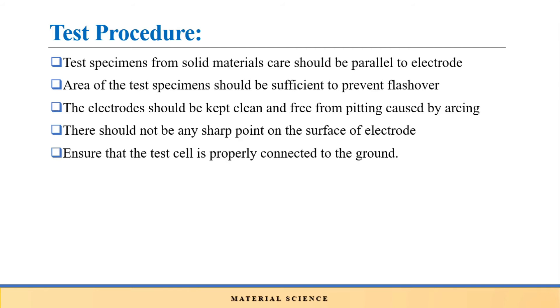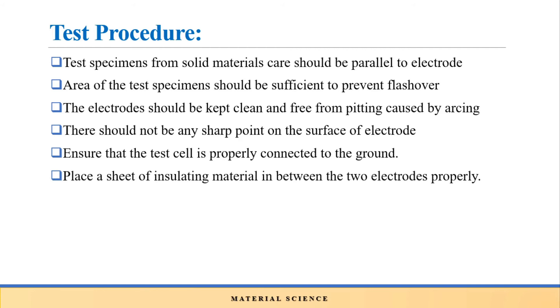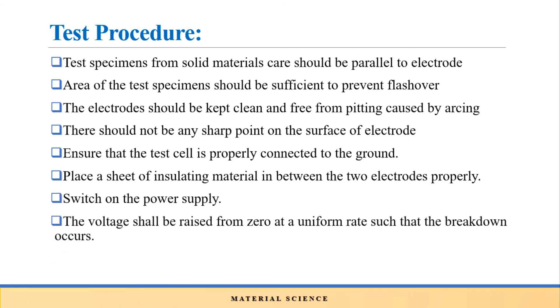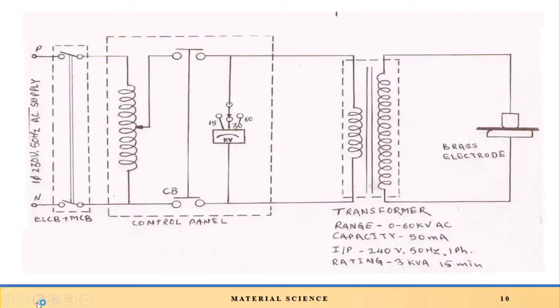Ensure that the test cell is properly connected to ground when working with high voltage. Place the sheet of insulating material properly between the two electrodes. Switch on the power supply and raise the voltage from zero at a uniform rate — for example, 2 kV per second — such that breakdown will occur. Note down the exact breakdown voltage, from which you can determine the breakdown strength of the solid insulating material.